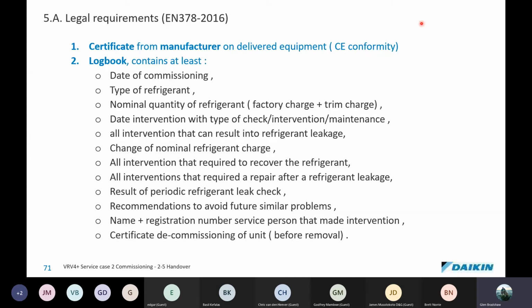Also, results of periodic refrigerant leak checks should be logged. Recommendations to avoid future similar problems, and the name and registration number of the service person that made the intervention, as well as the certificate to decommission a unit before removal. That's when a unit has reached the end of its life cycle.